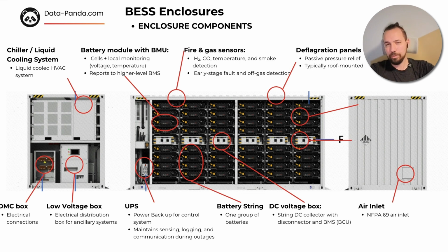So that's all about typical design. Again, if it's a 20 feet container, 5 megawatt hours, there could be small differences, but generally it will be the approach. And if we look into a customized solution, it will have all the same components. They could be placed differently, like a much smaller HVAC and so on, but the general approach and general components will stay the same.